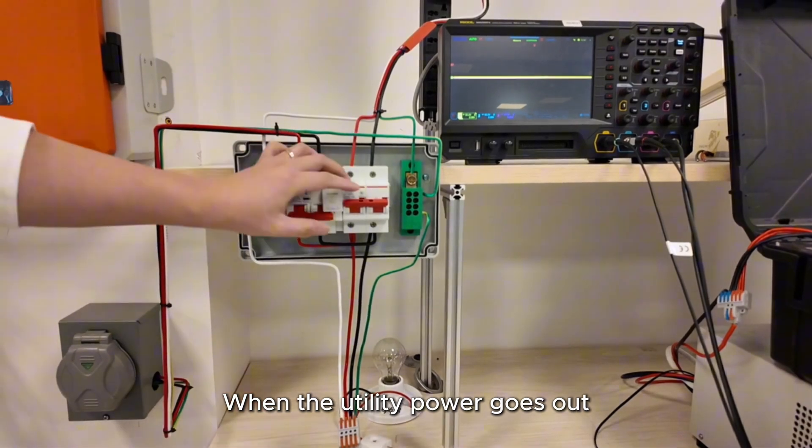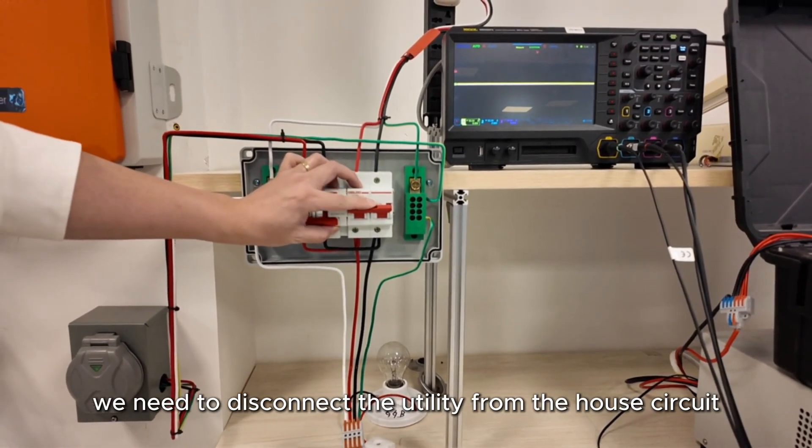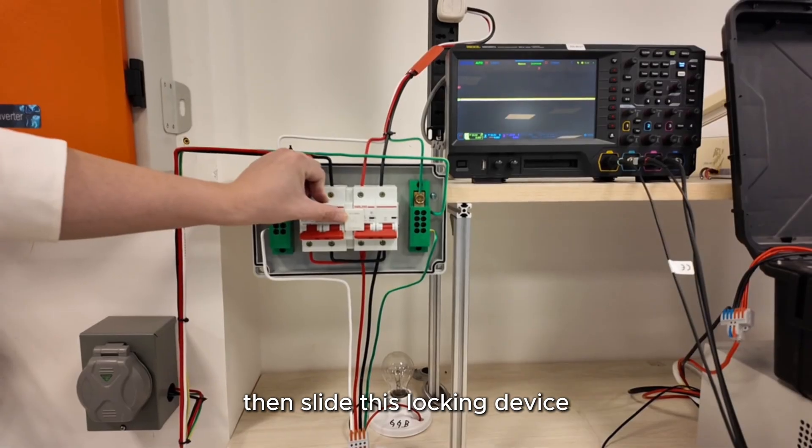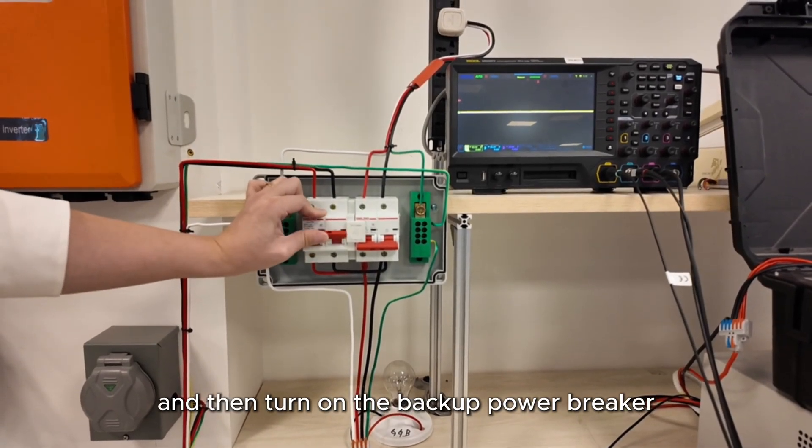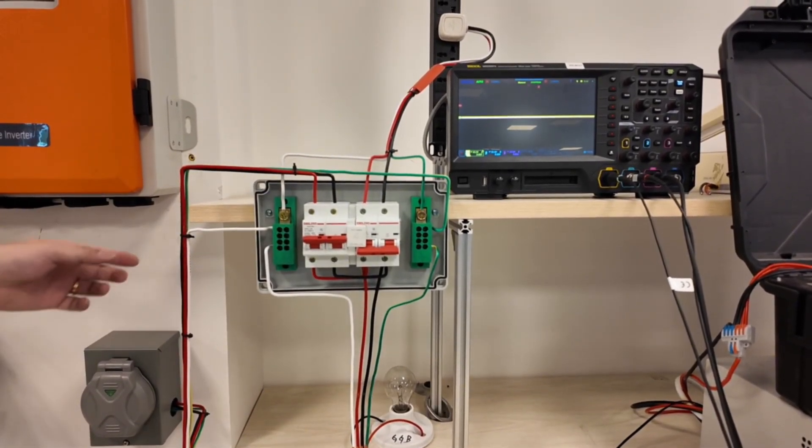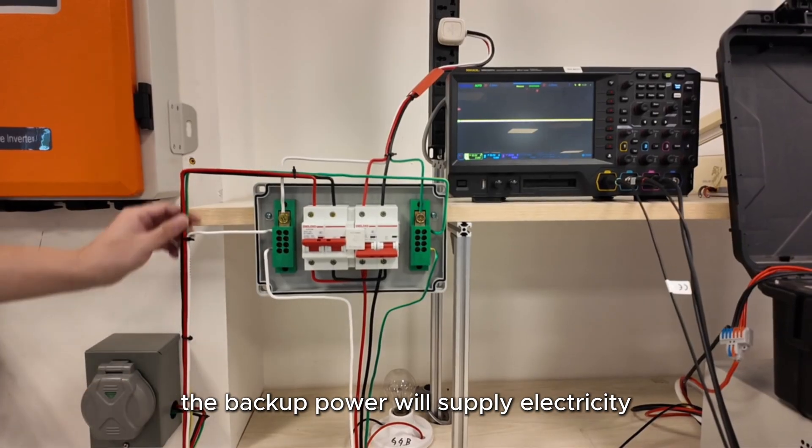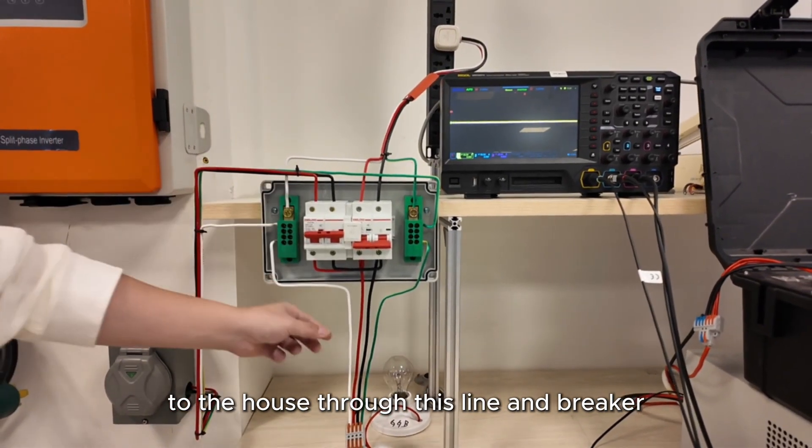When the utility power goes out, we need to disconnect the utility from the house circuit, then slide this locking device and then turn on the backup power breaker. At this point, the backup power will supply electricity to the house through this line and breaker.